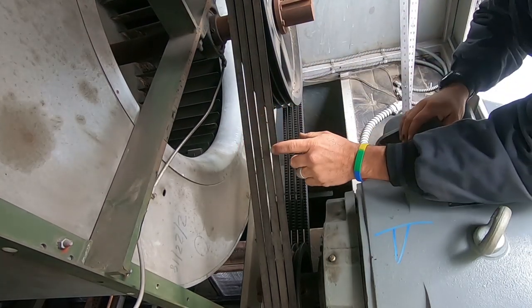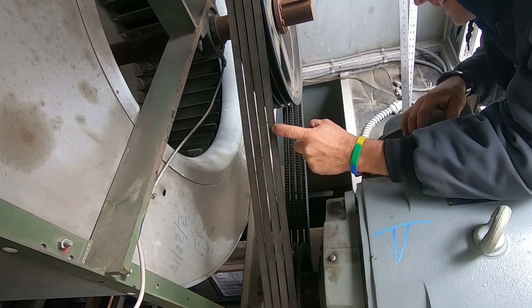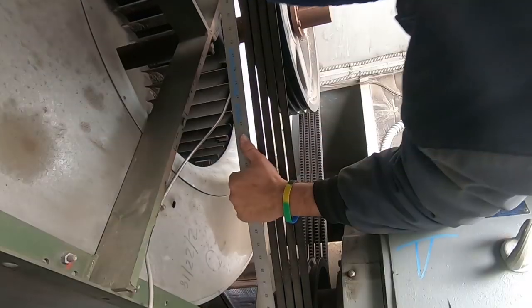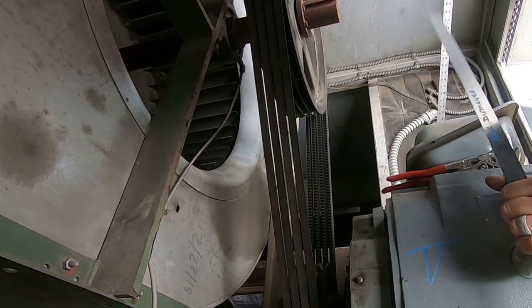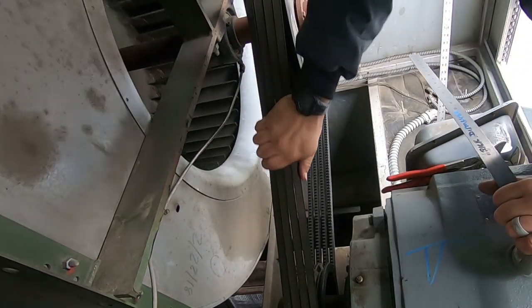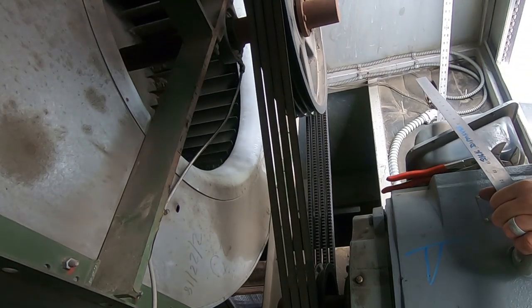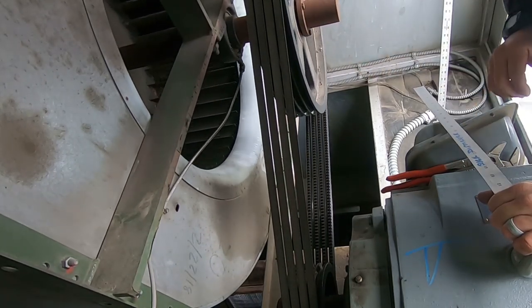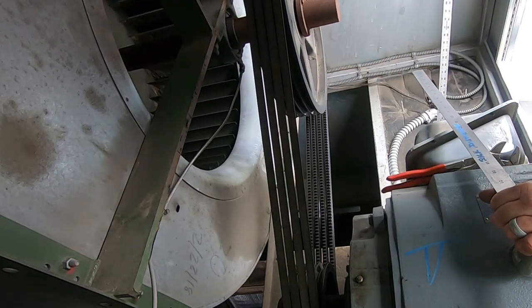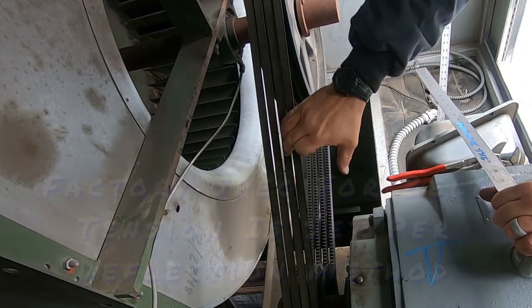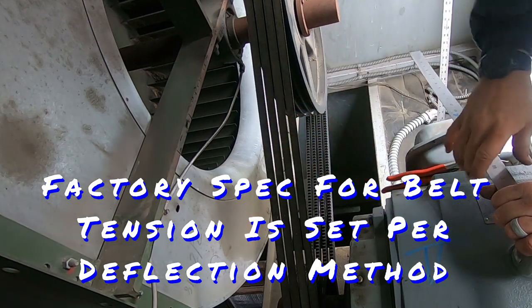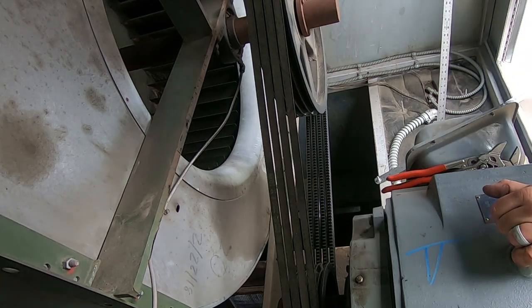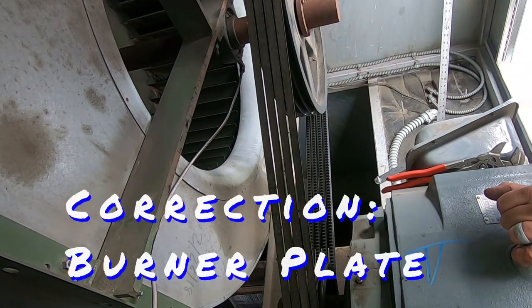Make sure you do your lockout tagout too. This thing will take your arm off and throw you off the side like it ain't nothing. Alright, it's pretty uniform. Also need to check our static pressure across the blower housing.